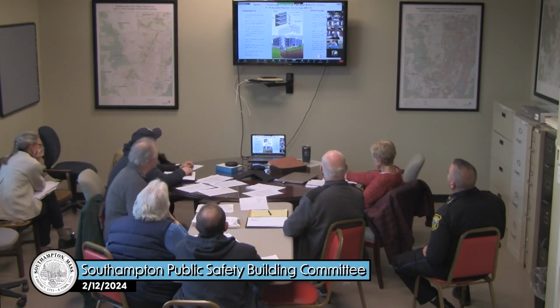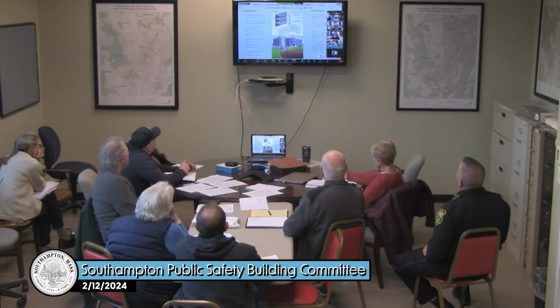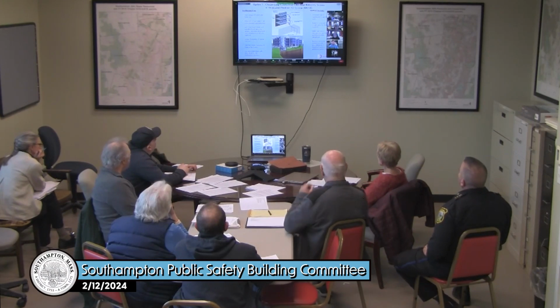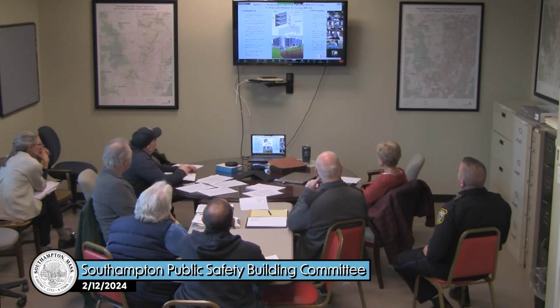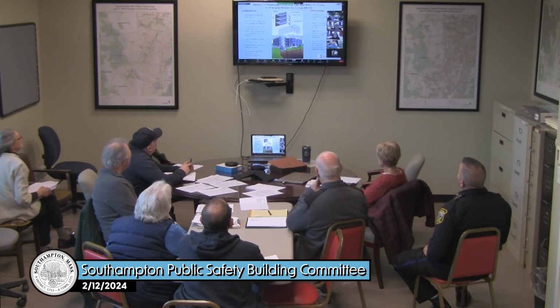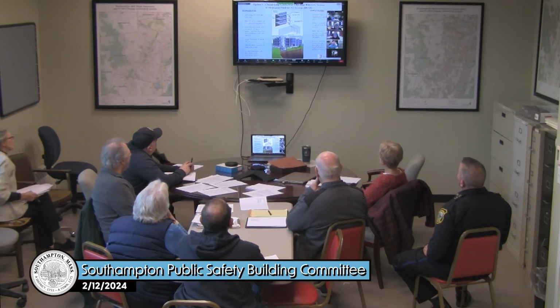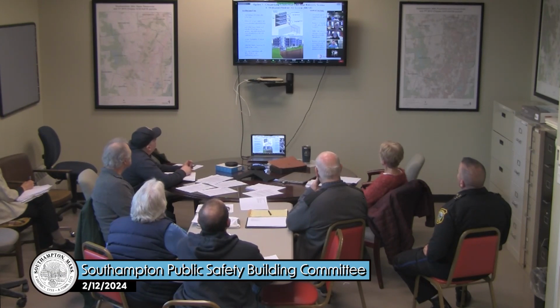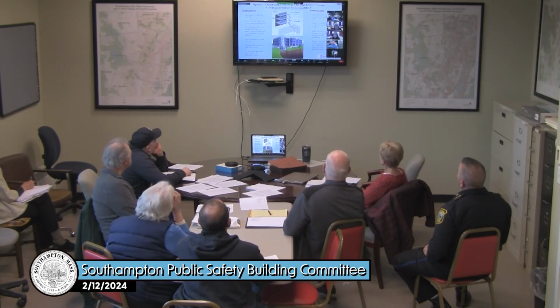You can use geothermal with both water source heat pumps and VRF. Like the rooftop unit, we could provide a water source heat pump heating and cooling section, which would receive the geothermal water directly, further increasing energy efficiency and lowering your EUI. Of course, that comes with a higher capital investment, requires increased site coordination, higher automatic temperature controls for geothermal plants, and increased maintenance.